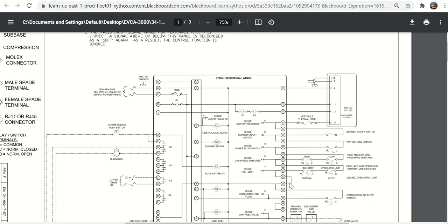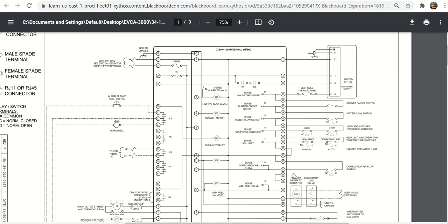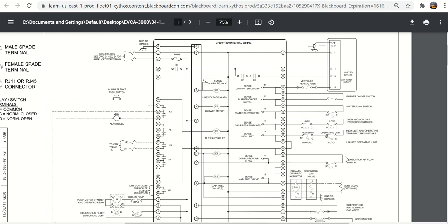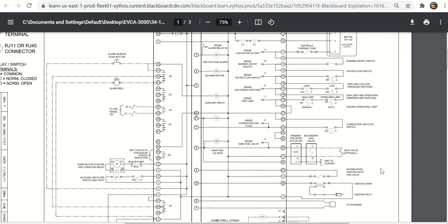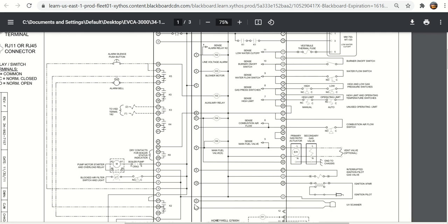You've got another jumper here for unused operating limit circuit. Comes down here to the combustion air switch. If the combustion blower is not running, you wouldn't have that. Through the function of the flame safeguard, once it sees all of those and you get power on terminal number 7, it goes through the ignition sequence. Terminal 9 is your main fuel valves. 8 is your pilot gas valve. 10 is your ignition transformer. G and F here, that's your UV scanner.